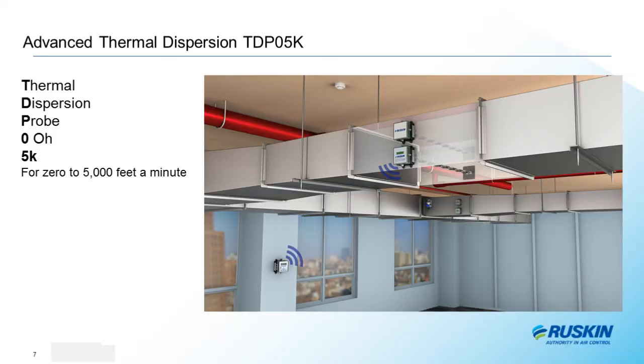What the heck is a TDP05K? Get it? It's a thermal dispersion probe, 0 to 5,000 feet a minute. That's the range. That's what this thing is. What is it? It's the most advanced thermal dispersion air measurement system available today. This new system has no limits.